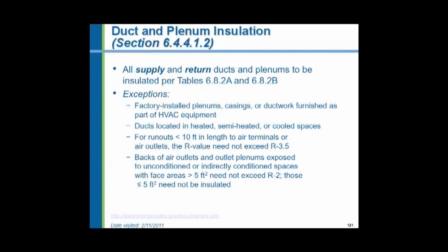Return and supply ducts and plenums have to be insulated, and there are a number of exceptions. And the ducts located within the heated, semi-heated, or cooled spaces. Now the operative word there is spaces. So if you had ductwork above a ceiling in the corridor, you'd have to insulate it. But if for some reason that ductwork was exposed within the living space where the people were, it would look very bad, obviously, but it might have to be for one reason or another. You need not insulate it. And you find this in many bars and restaurants now, where the ductwork is exposed. Spiral ductwork, very sturdy. It's painted. It's exposed. Sometimes it's painted in bright colors to be part of the decoration. Sometimes it's painted in flat black to disappear into the ceiling spaces.